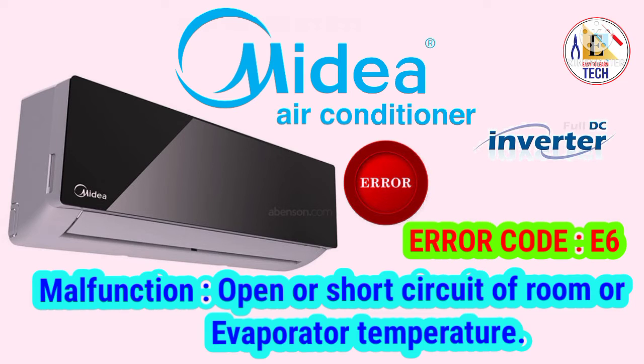When you see the error E6, it means open or short circuit of your room or evaporator temperature sensor, or the sensor is faulty. First of all, you have to check the placement, if it is placed properly in your evaporator coil or not. If it is not placed properly, place it properly and see if there is an error or not. If there is no error, it means there was an issue of placement.